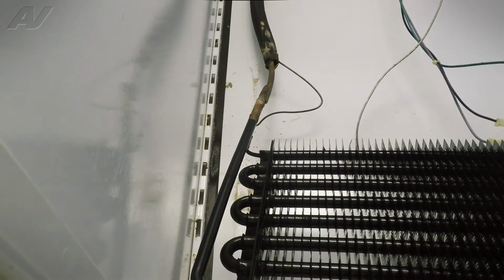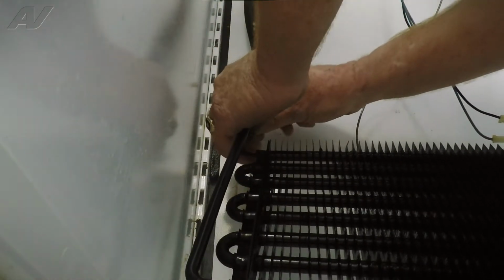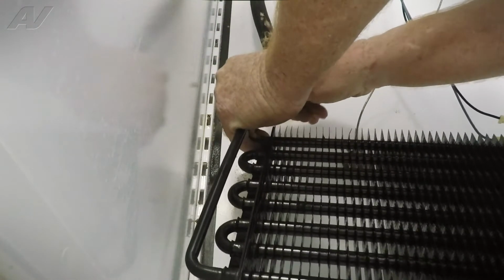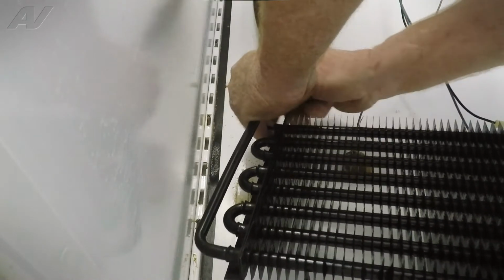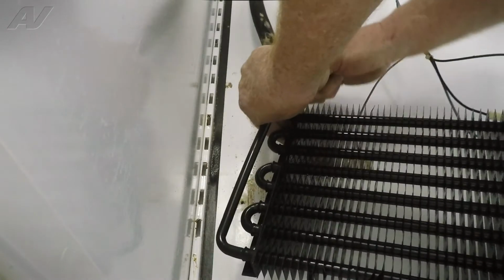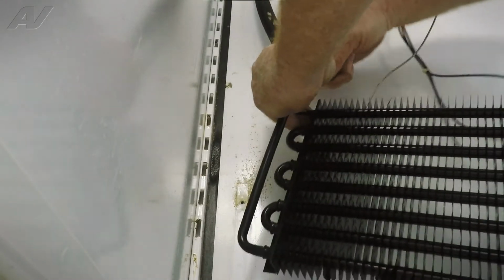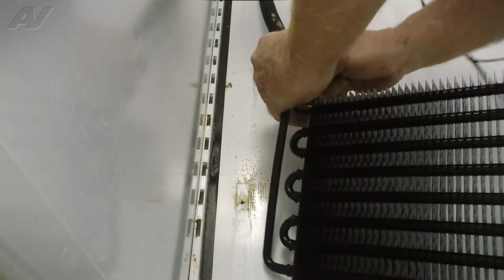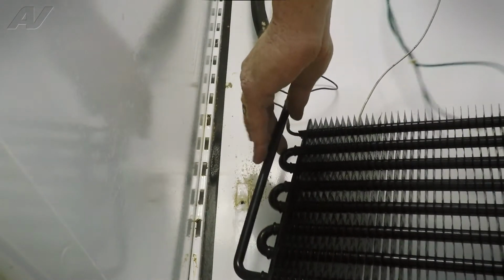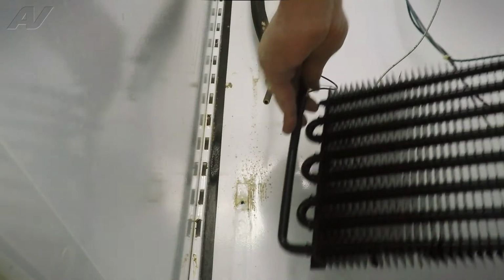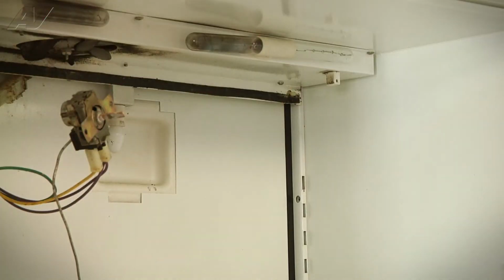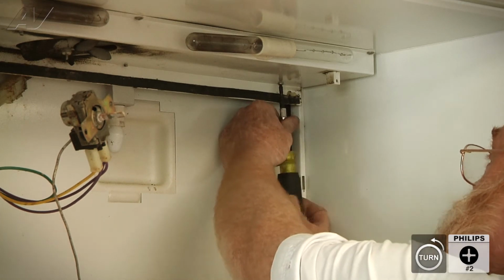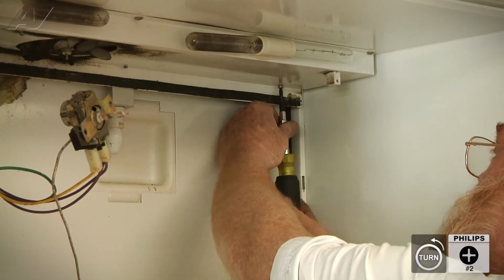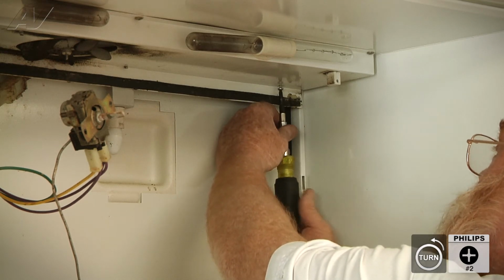Now, because we're replacing the heat exchanger, I'm just going to take the capillary tube and bend it back and forth until it breaks. Or you can take a pair of diagonal cutting pliers and achieve the same result. Just snip it and the evaporator is removed. We'll set that aside. The next step is I'm going to drop this panel so that it does not impede my removal and installation of the heat exchanger tubing.